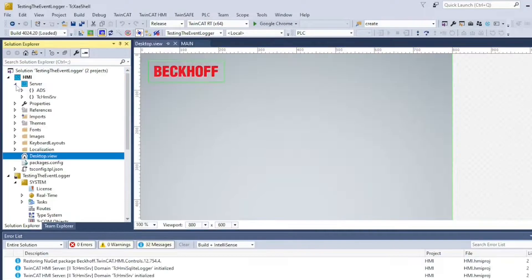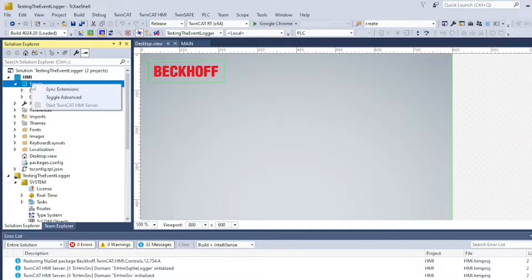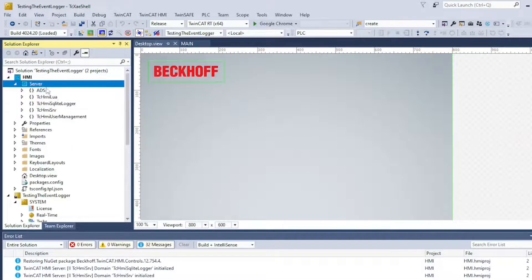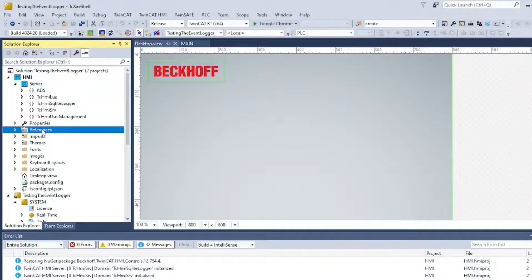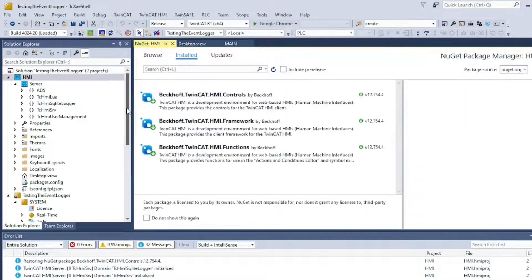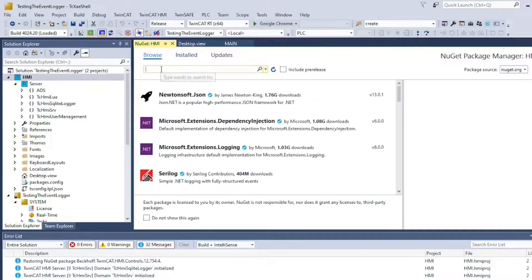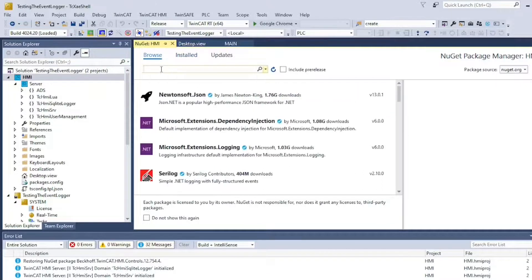We want to add an extension so we can visualize messages and alarms on the HMI. Under Server, select Toggle Advanced to see all the current extensions of your project. Click on your references and manage NuGet packages. Select the tab Browse and type event logger. Remember, keep the versions consistent.